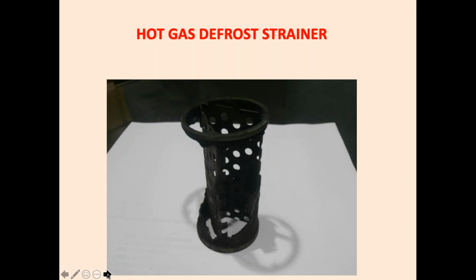This hot gas defrost strainer, because of the heat, has gone totally damaged because the pressures and temperatures for the defrost are not properly maintained. Maintain a low pressure for defrosting, not more than 6 kg, 7 kg maximum. Don't allow full discharge pressure for hot gas defrost.